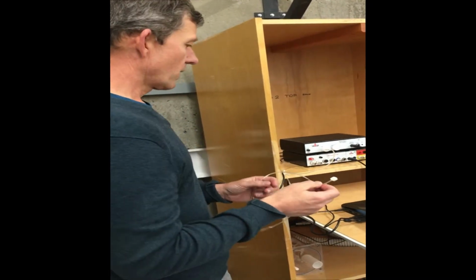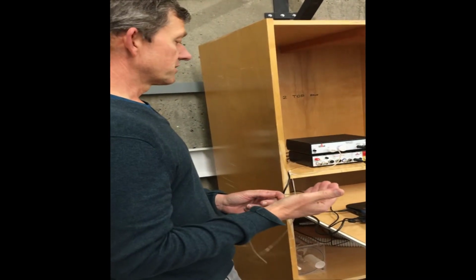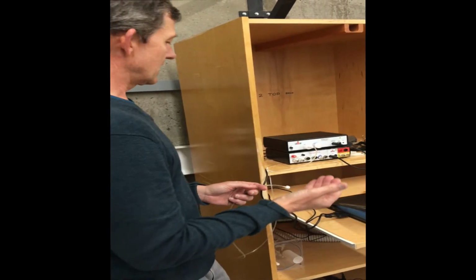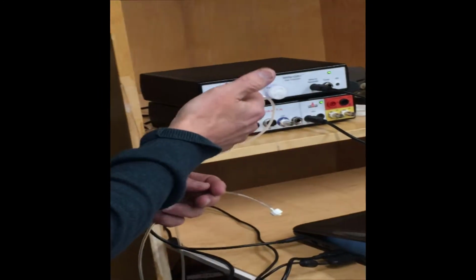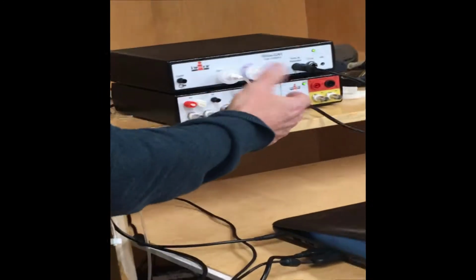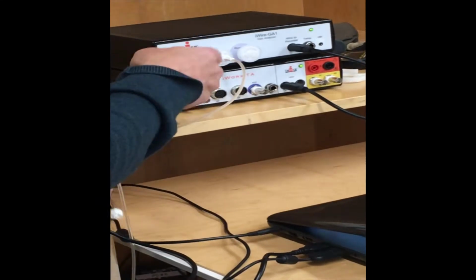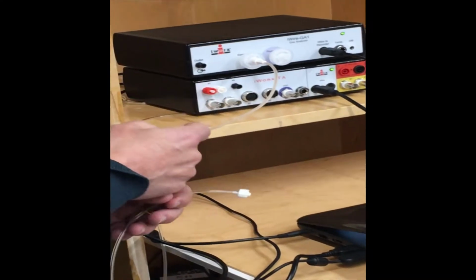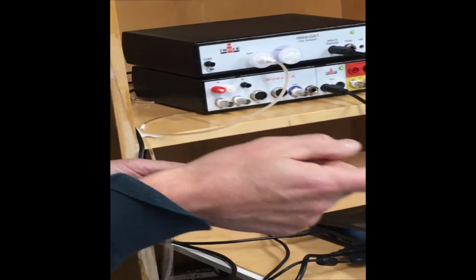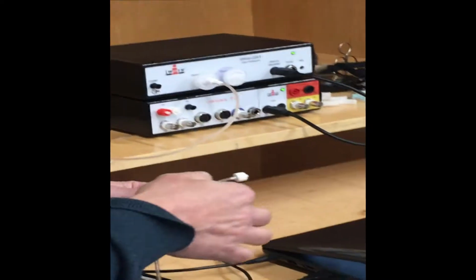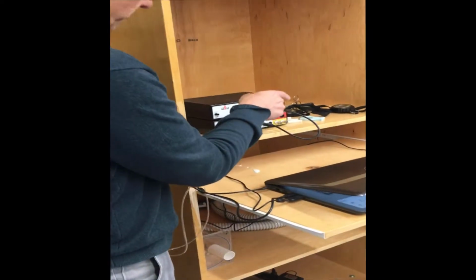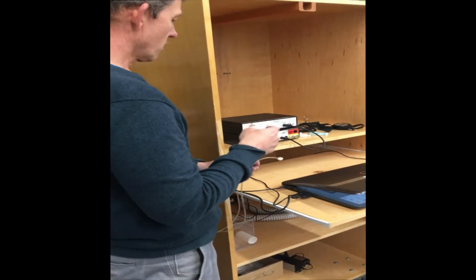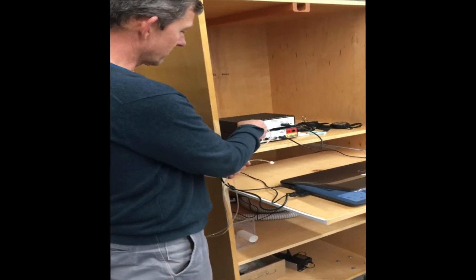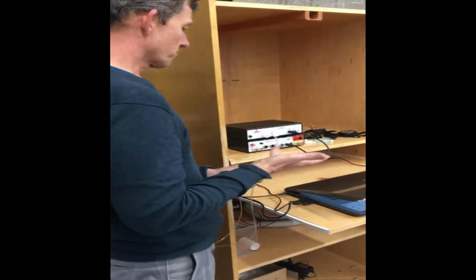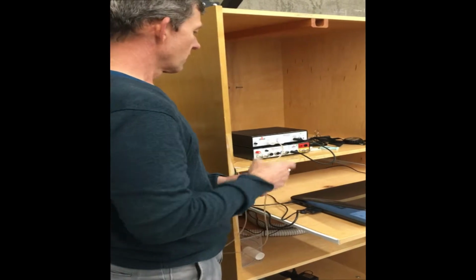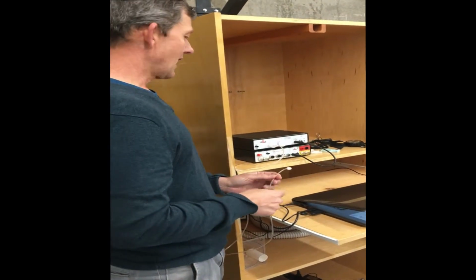So it's hooked up and it's ready to go, but like everything else that we do, the very first thing we need to do is calibrate it. The way you calibrate it is that you run room air through it, and then you run a calibration gas through it. This has two different ports, one for room air and one for the sample line. In this case, we're going to put the calibration gas through. There are two filters on each port, and the reason for that is you don't want any contaminants coming in and getting into the sensors. It is going to draw air in through the room air side for 10 seconds. Then it's going to draw air in through the sample side. The calibration gas is going to go through the sample side for approximately 15 seconds, and then based on that, it's going to calibrate, and then we know that we're going to get accurate readings.